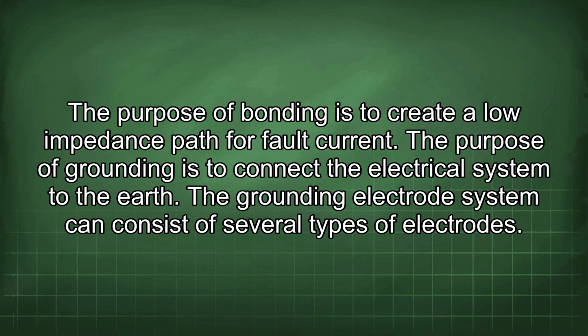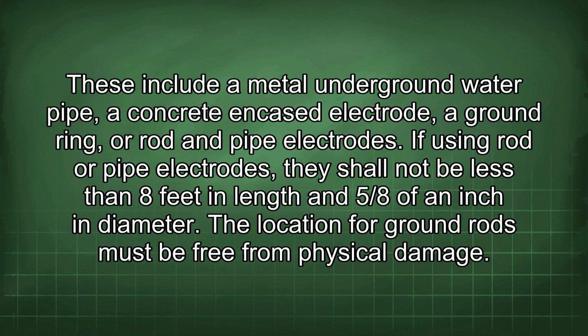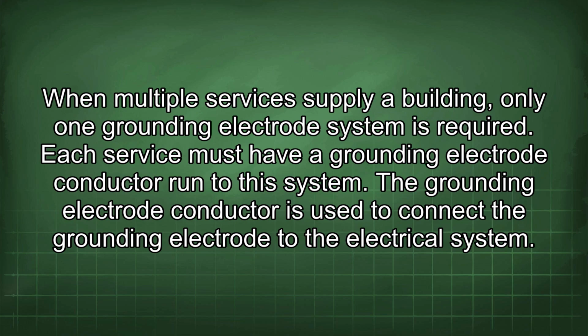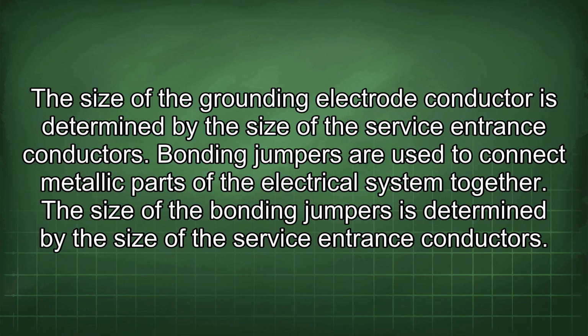The grounding electrode system can consist of several types of electrodes. These include a metal underground water pipe, a concrete encased electrode, a ground ring, or rod and pipe electrodes. If using rod or pipe electrodes, they shall not be less than 8 feet in length and 5/8 of an inch in diameter. The location for ground rods must be free from physical damage. When multiple services supply a building, only one grounding electrode system is required. Each service must have a grounding electrode conductor run to this system. The grounding electrode conductor is used to connect the grounding electrode to the electrical system. The size of the grounding electrode conductor is determined by the size of the service entrance conductors.